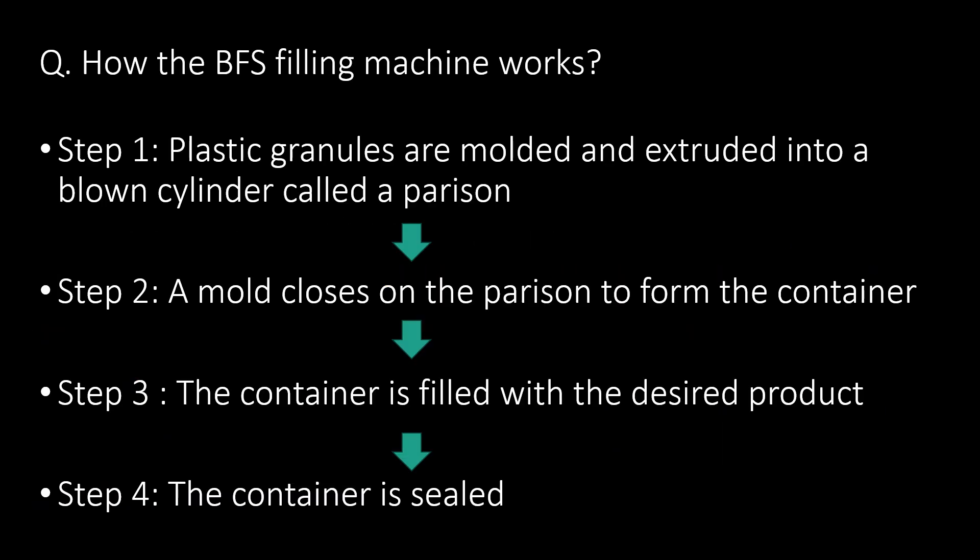How does the BFS filling machine work? Step one: Plastic granules are molded and extruded into a blown cylinder called a parison. Step two: A mold closes on the parison to form the container. Step three: The container is filled with the desired product. Step four: The container is sealed.